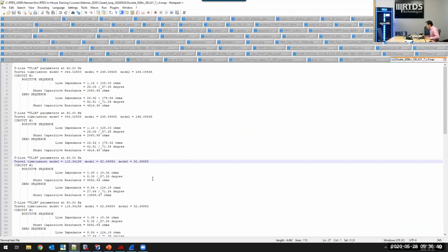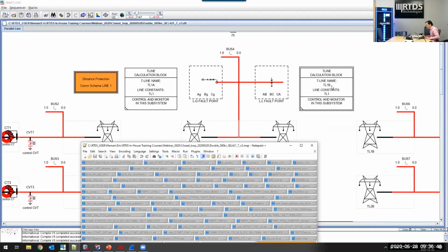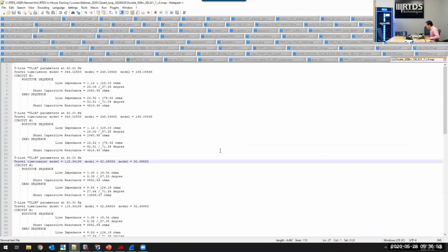Be careful that since 2 lines are used to model the protected line, in our case we have this TL1A and the TL1B together to model the whole line. The impedance of TL1A and TL1B need to be added up together to get the impedance of the protected line.